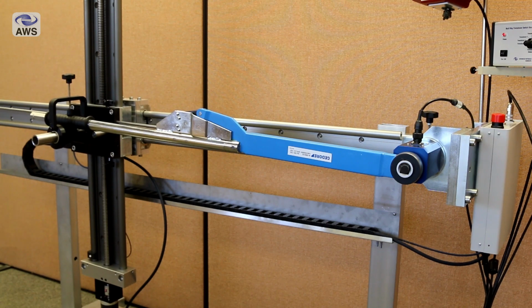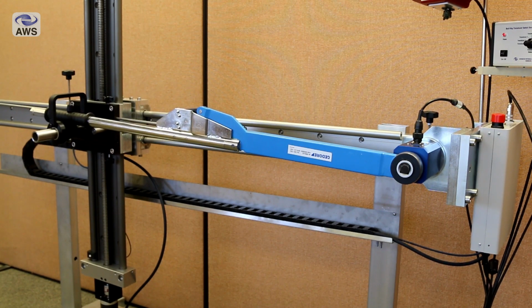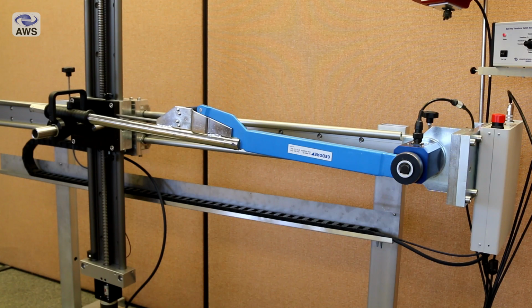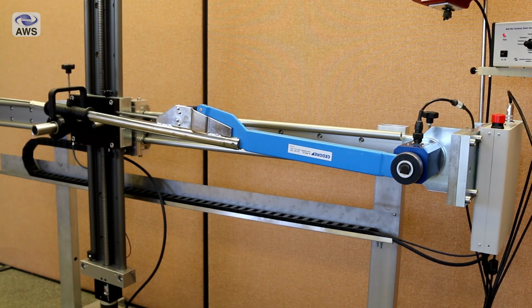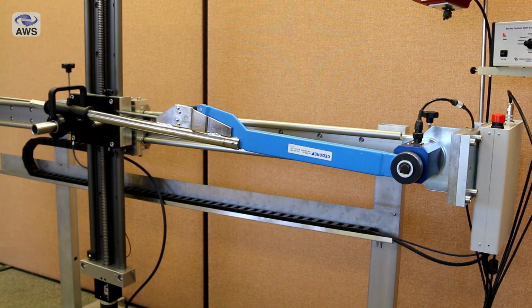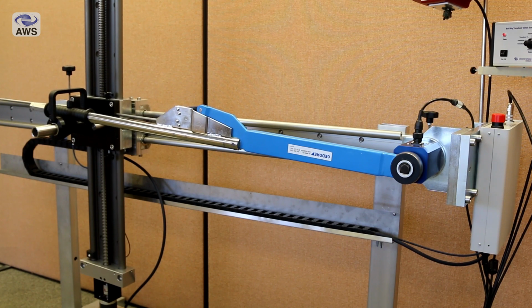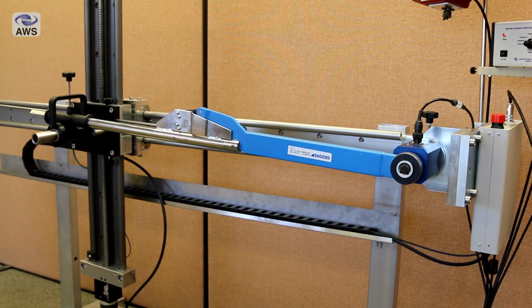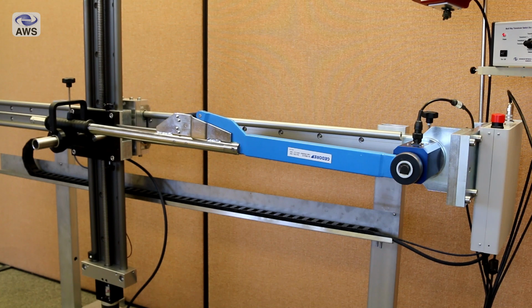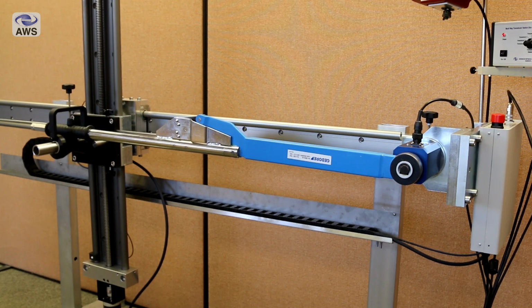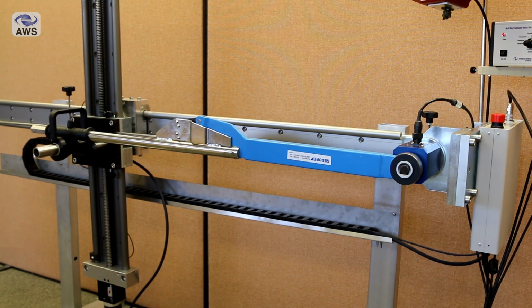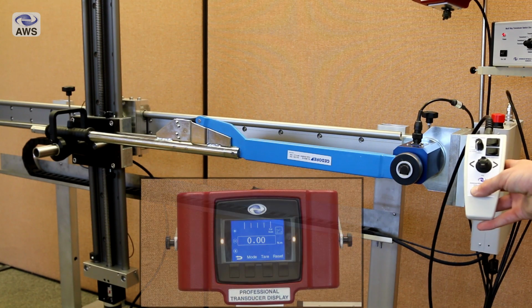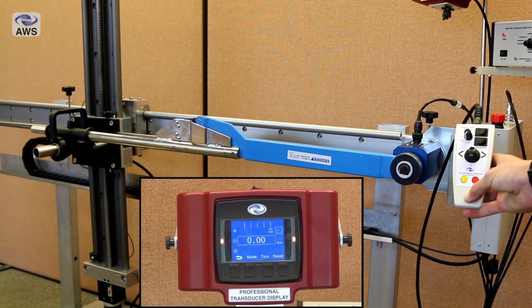When the wrench reaches 80% of the target torque, the machine slows down to the correct rate to meet the standard. That's the ISO 6789:2017 rules. When the wrench operates or clicks, the machine will stop and reverse automatically, coming back down until the torque reaches 0 again. To run the machine again, all you have to do is press and hold the yellow button on the handheld for half a second and release.